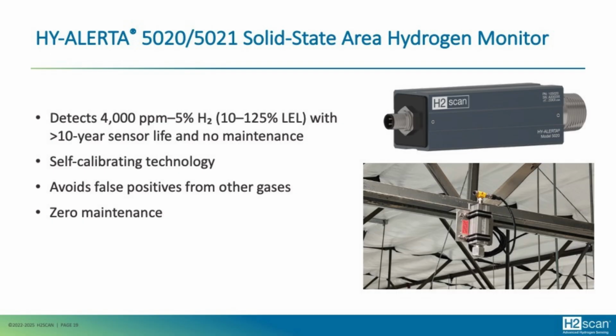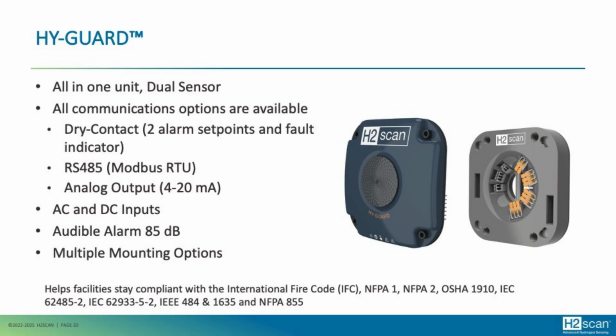Then we have our newest sensor, which is the HY-GUARD. The HY-GUARD is an all-in-one unit. It has all of the communication platforms built into one unit. It also mounts to a standard J-box, which makes it very easy for installation. It has Wago connectors that you can basically strip the wire, put the wire in, and flip the tab down, and it is secure. And so that way there are no tools needed to connect your power and communications. It has AC and DC inputs. It has audible alarms. You can also have other mounting options such as DIN rail, magnets, and wall mount for this unit.